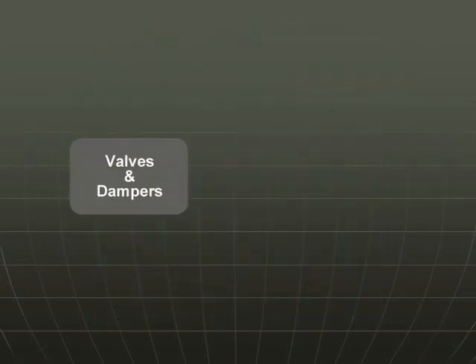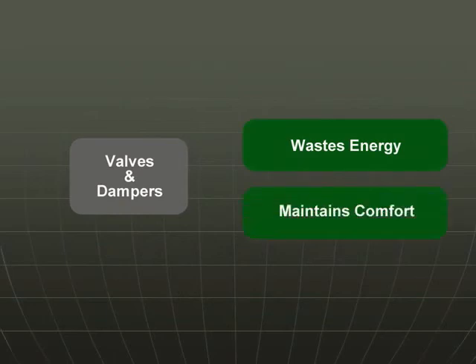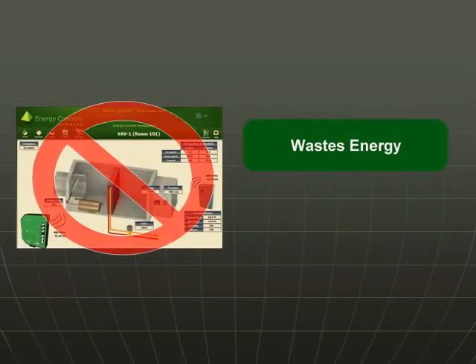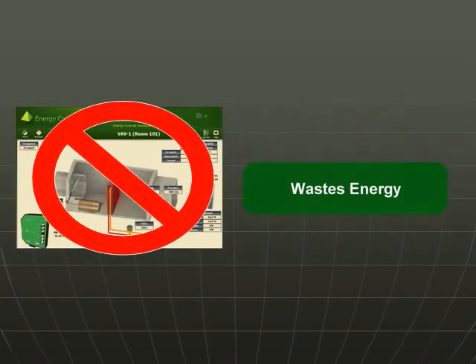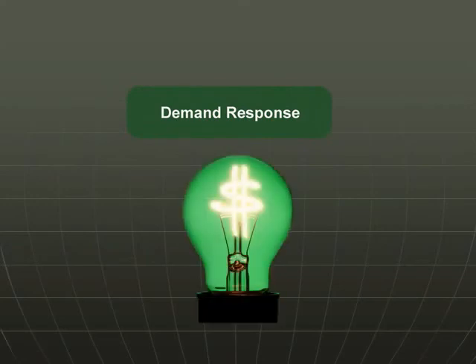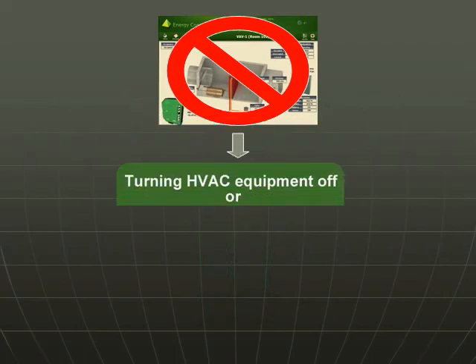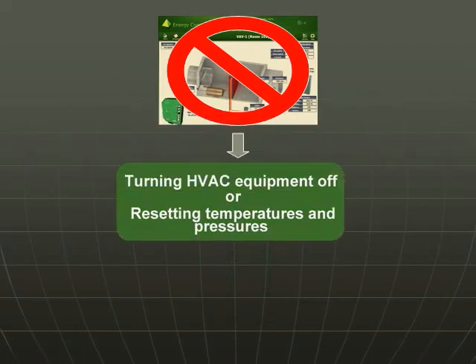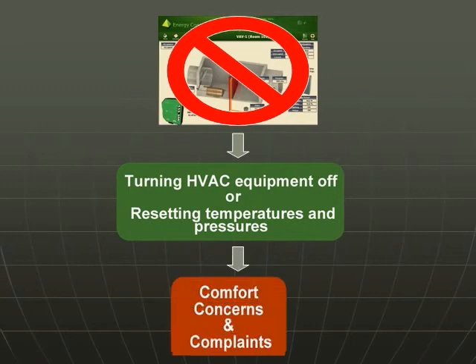There are various conditions where valves and dampers are wasting energy daily but are able to maintain reasonable comfort conditions. Without being able to monitor the entering, supply, and room air temperature conditions, these dampers and valves can continue to waste energy and money. Demand response program given through utility companies is a very lucrative opportunity for building owners. Without knowing the temperatures of your zones, turning any of your HVAC equipment off or resetting temperatures and pressures can cause comfort concerns and complaints throughout the facility.